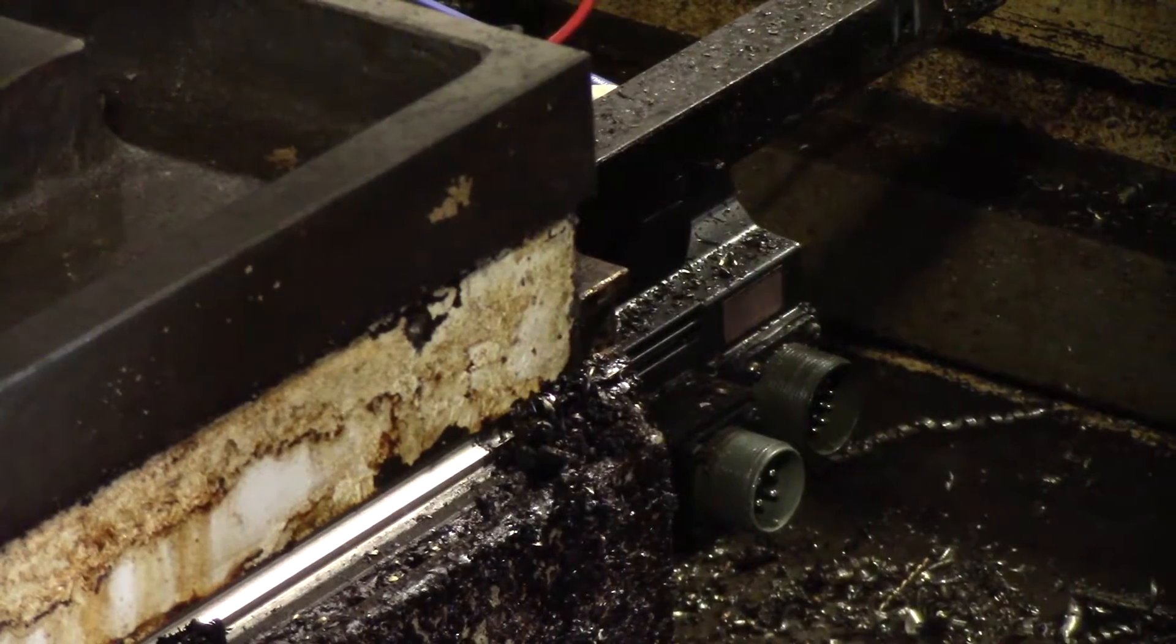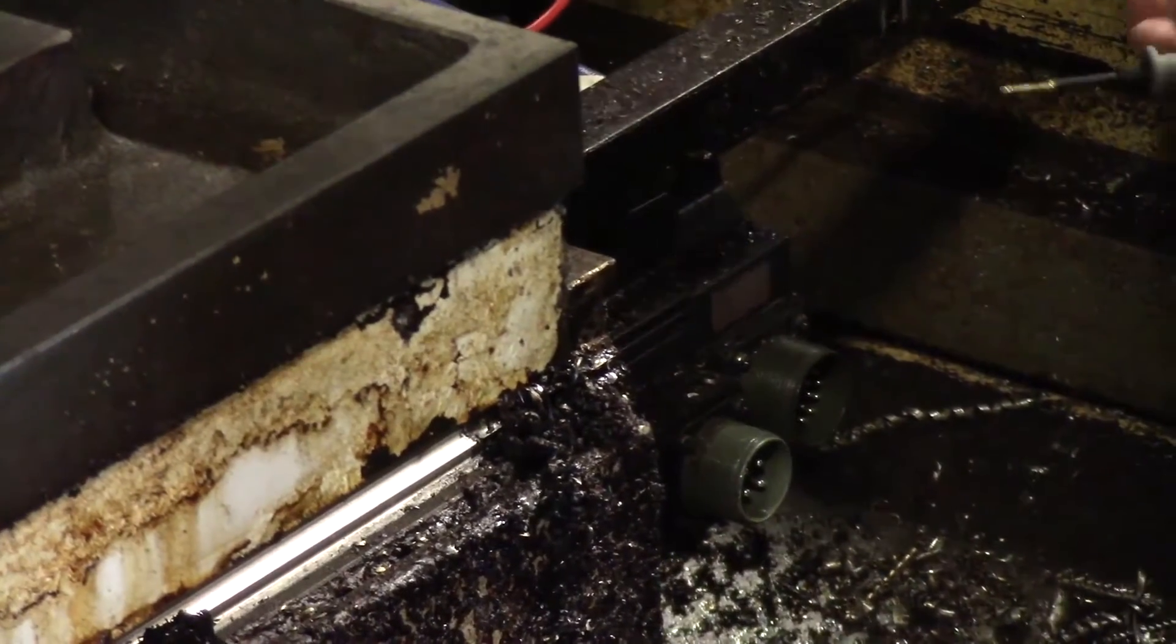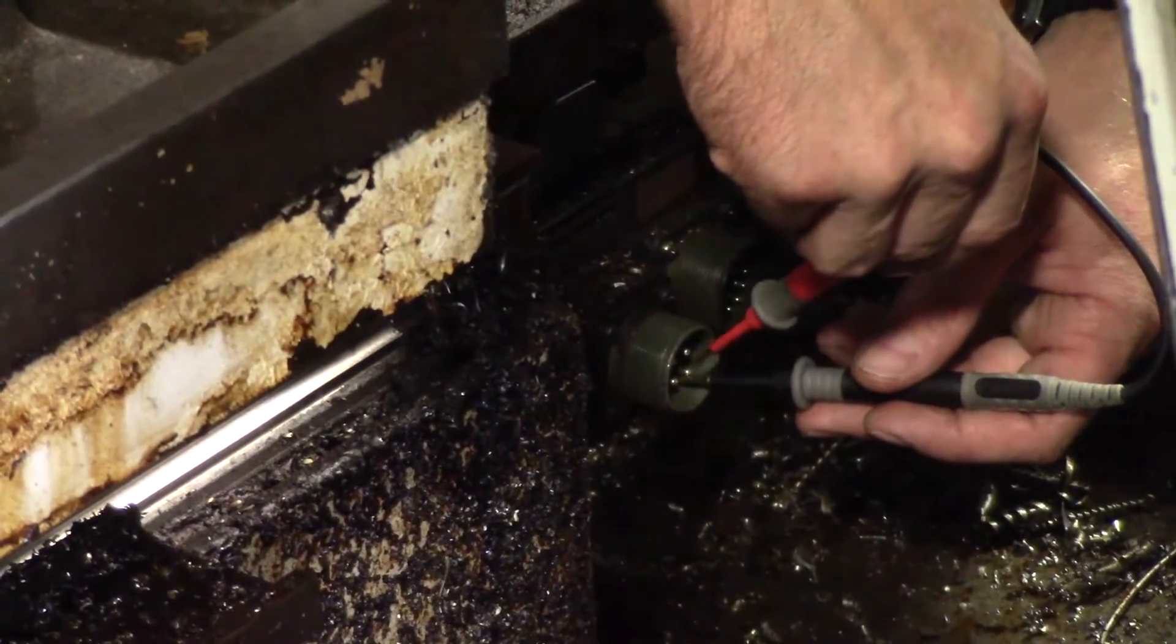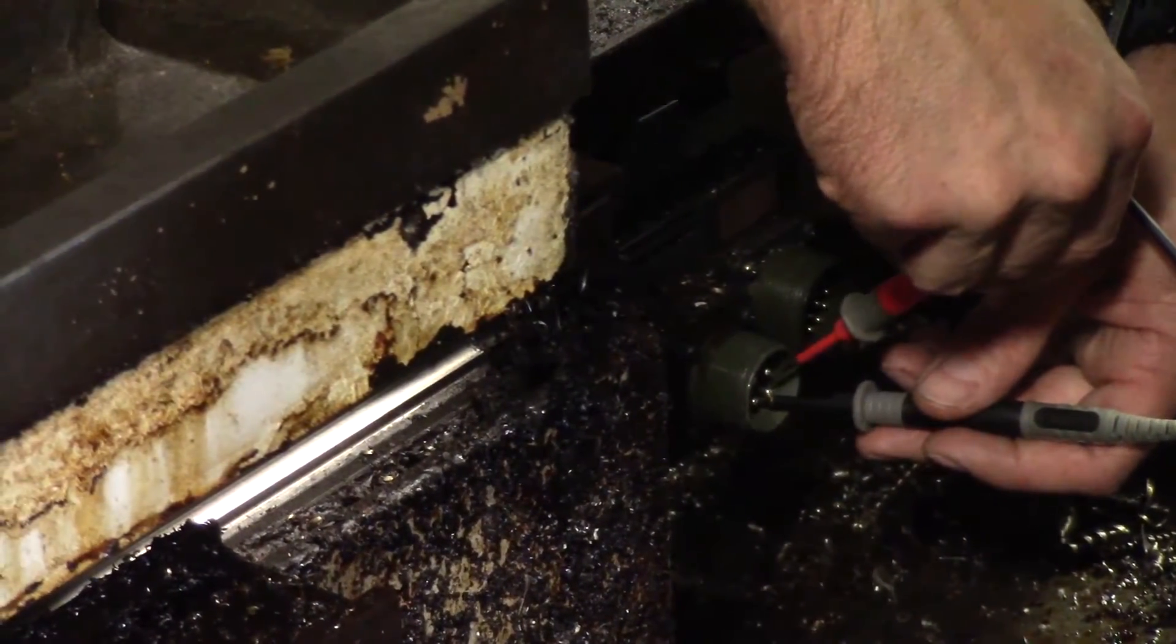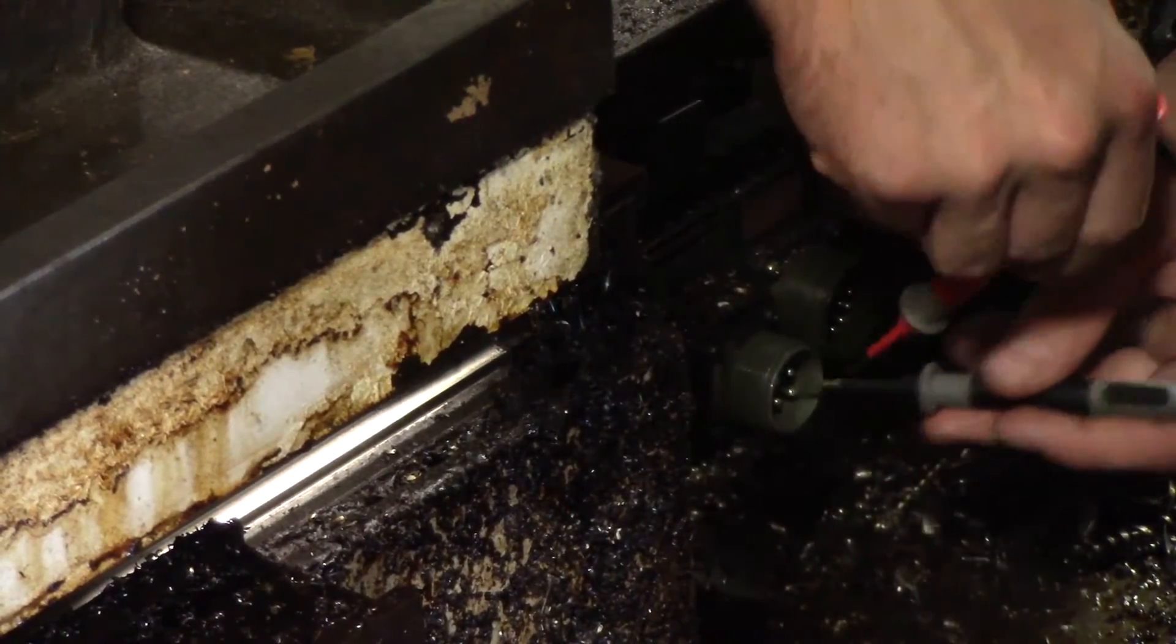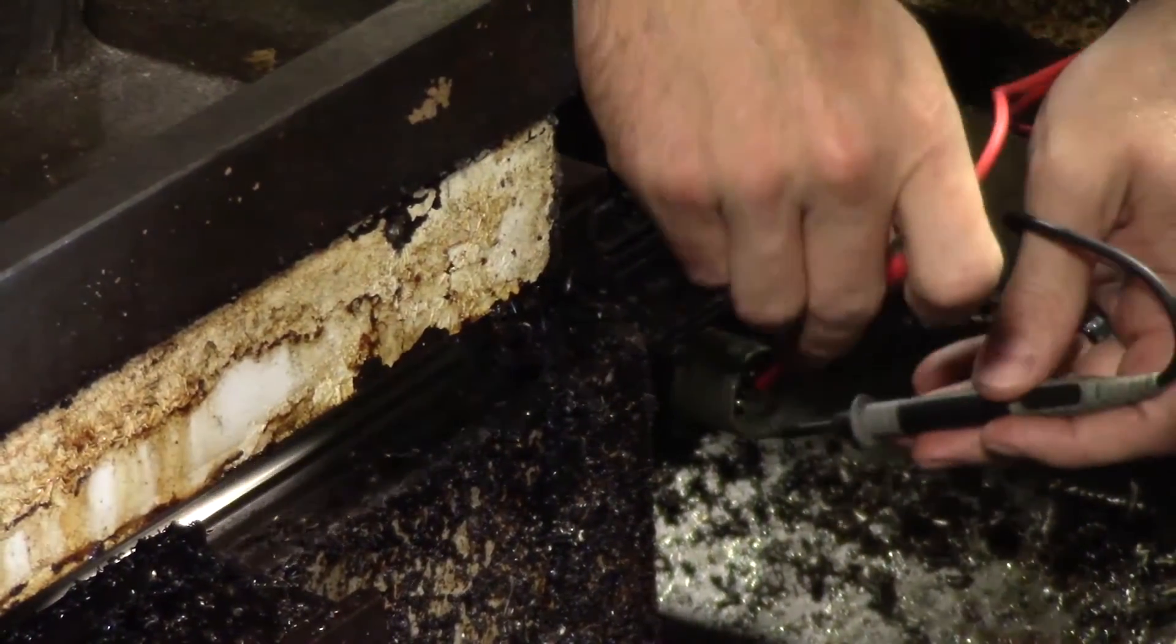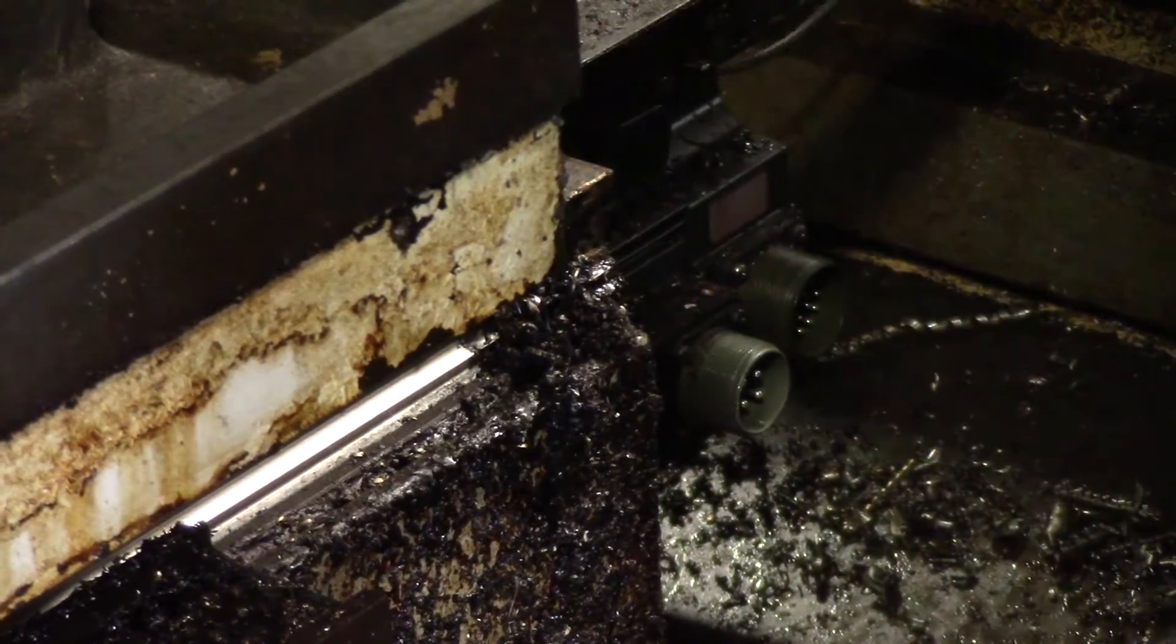Four thousand, four thousand, four thousand. Okay then at this point we should have found a grounded motor. Don't forget to discharge that coil.